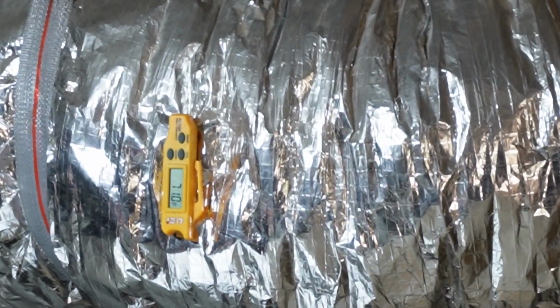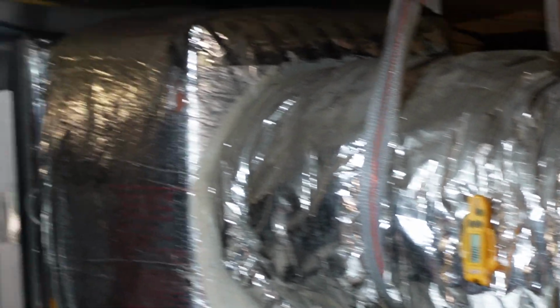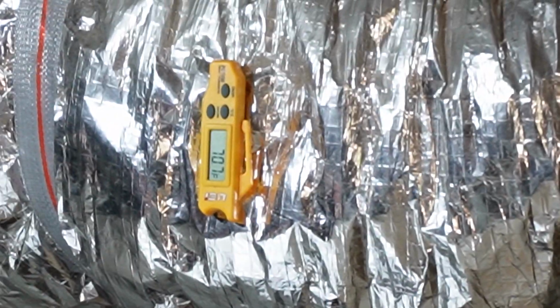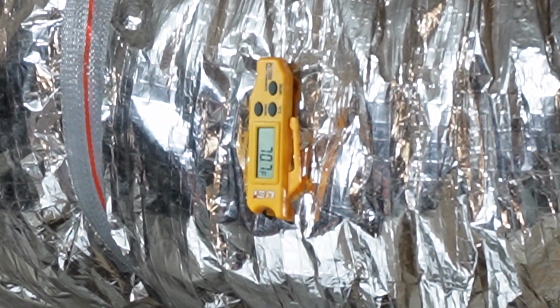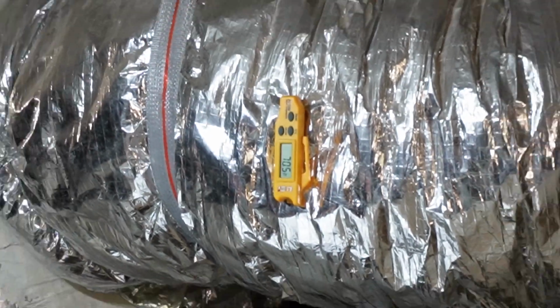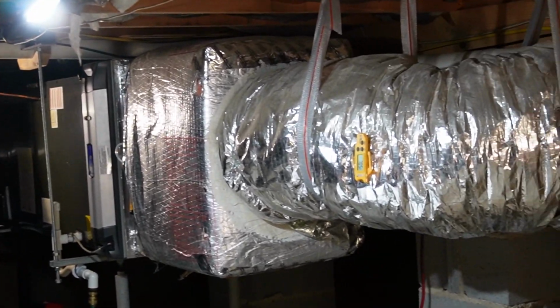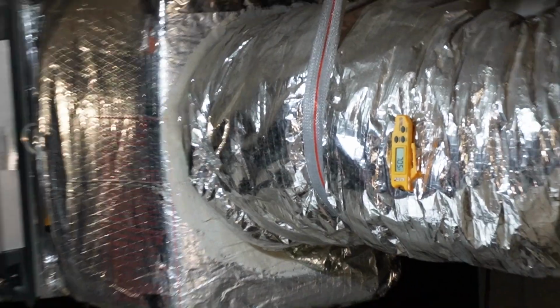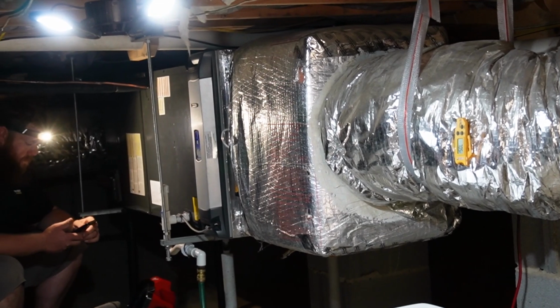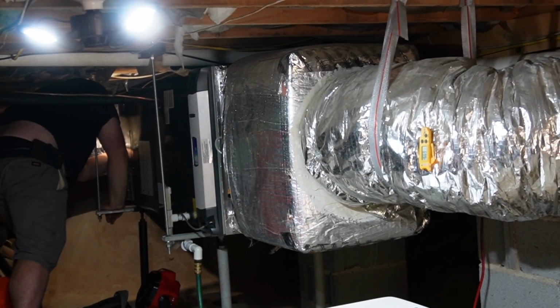Got some probes in to check the split, one there, one over on the supply. See if we can get zoomed in. We got 70 coming in - what do we got coming out? 53. 70 to 53, ladies and gentlemen, that is 17 degrees. Besides the wiring crap show, this thing's fired up pretty nice. All right, so we ended up with a 19 degree split.